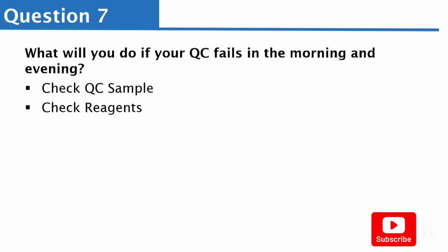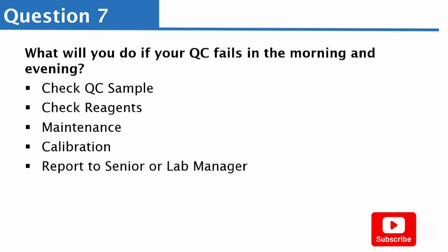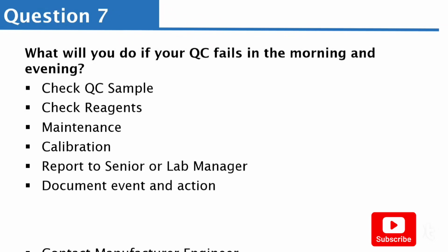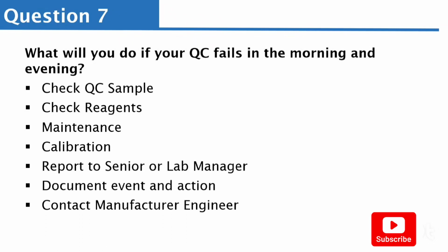You're going to check the reagent, and you're going to do maintenance where possible. You're going to do calibration where possible. You're going to report to the senior or laboratory manager, obviously, and you're going to document the event and the action that you have taken, okay? And then you can contact the manufacturer engineers to come and look at it.